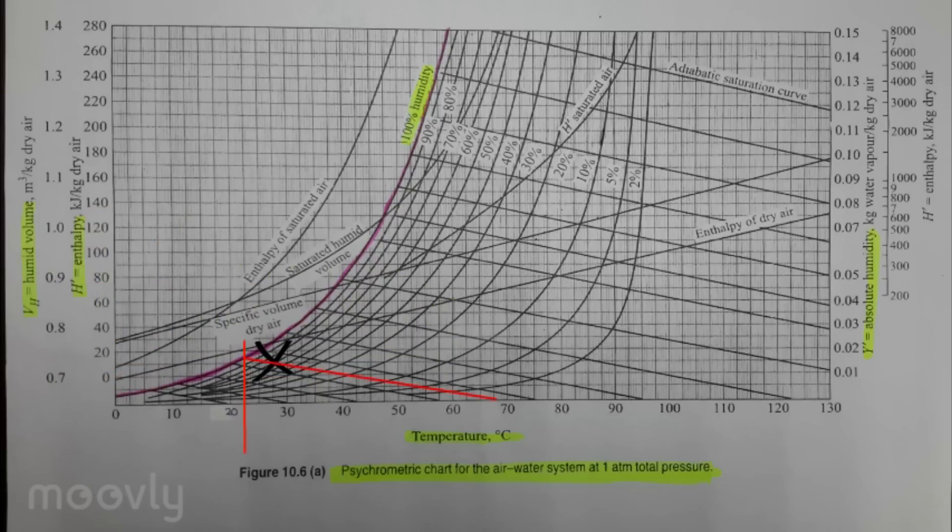Read enthalpy when the wet bulb temperature vertical line intersects with the enthalpy of saturated air curve. Enthalpy is around 64 kJ per kg.